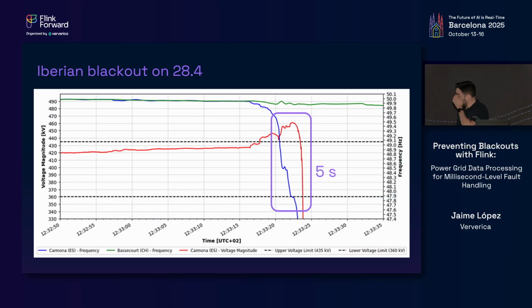So going a bit deeper into this, what this shows, exactly like you can see in the timestamps, is these 5 seconds of a node in the grid, which is in the south of Spain, in Carmona, Sevilla, where suddenly the voltage zooms and goes to basically zero. And a little bit before that, the frequency starts to show something going on. Meanwhile, the green line is a node in Central Europe, which was far away from this and probably had a better protection infrastructure. It barely saw any dip here. They saw some oscillation, some resonance, that's fine, it can be managed.